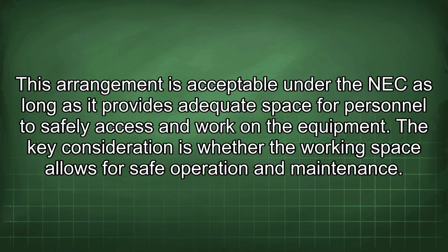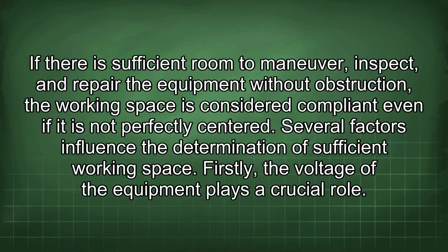This arrangement is acceptable under the NEC as long as it provides adequate space for personnel to safely access and work on the equipment. The key consideration is whether the working space allows for safe operation and maintenance. If there is sufficient room to maneuver, inspect, and repair the equipment without obstruction, the working space is considered compliant even if it is not perfectly centered.